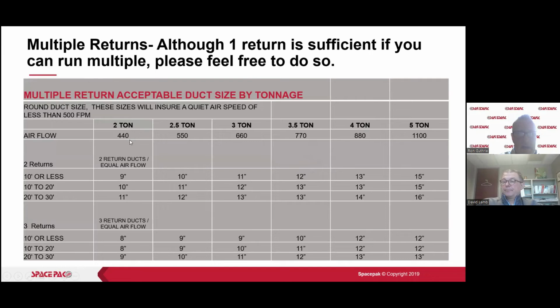Here's how that works again. Unfortunately, we're at 440, here is what we're showing. Okay, so we're showing the minimum airflow. You want to try to be at 250 per ton, so we'd be at 500 right here.